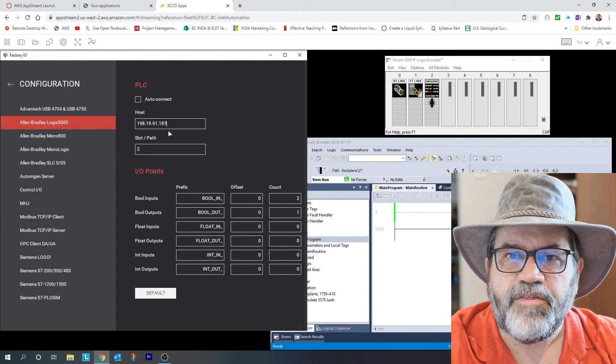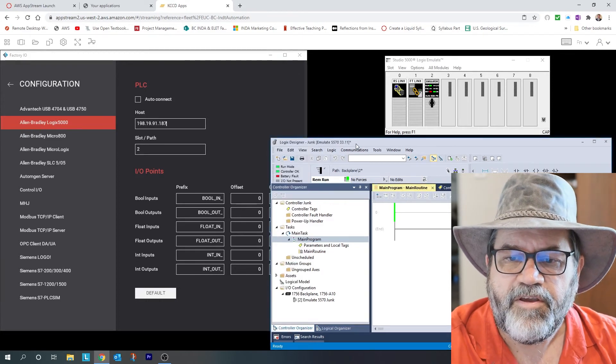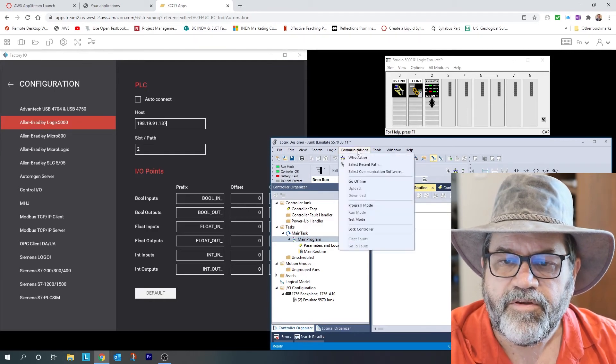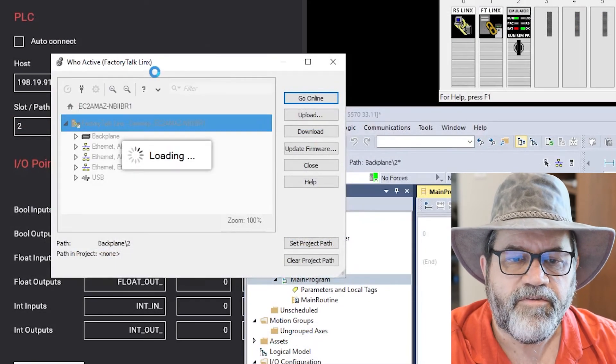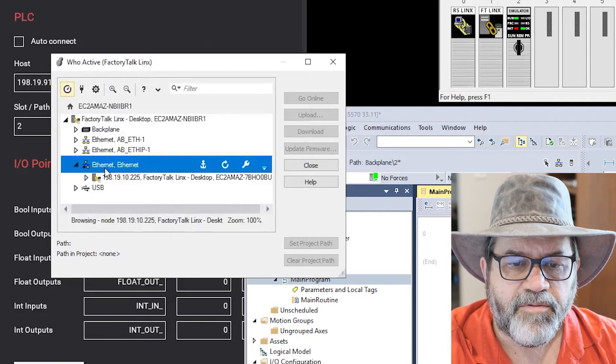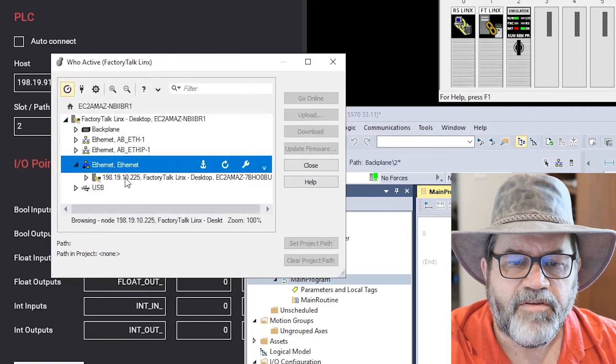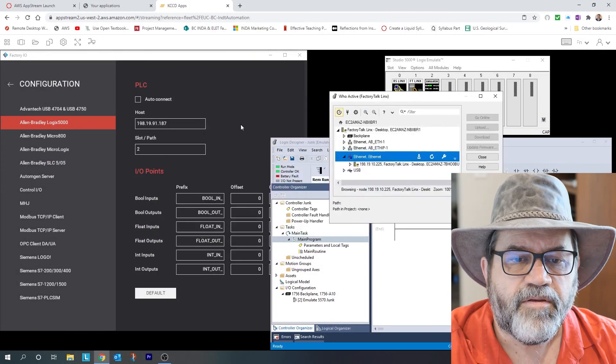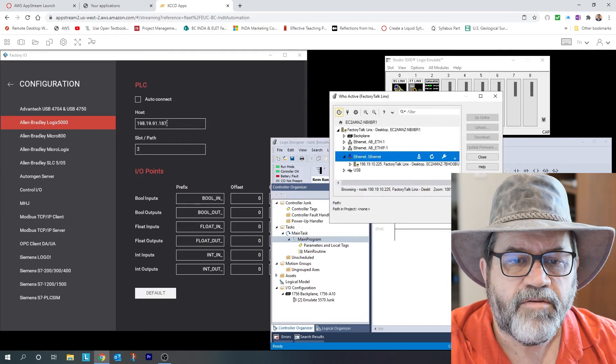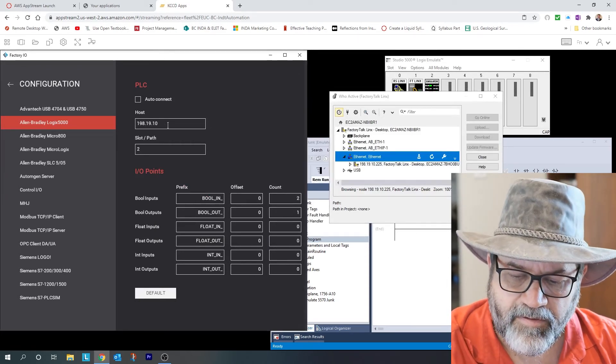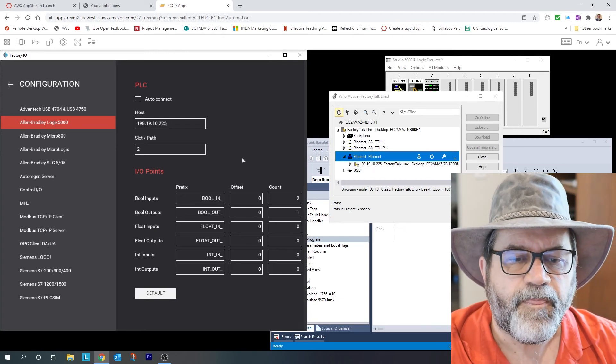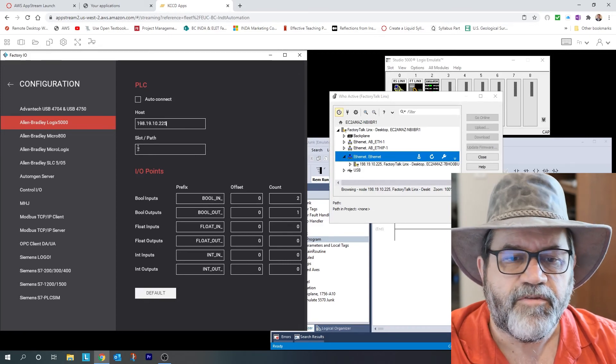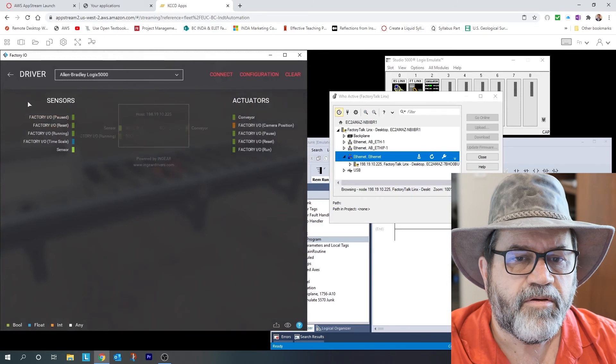And to do that, I use one of our communication softwares. So I can go communication, who active again, and that brings up FactoryTalk Linx. And I'll just expand the ethernet here, and I can see it's 198.19.10.225. So I need 198.19.10.225. I also need to make sure that it knows that the controller is in slot 2.